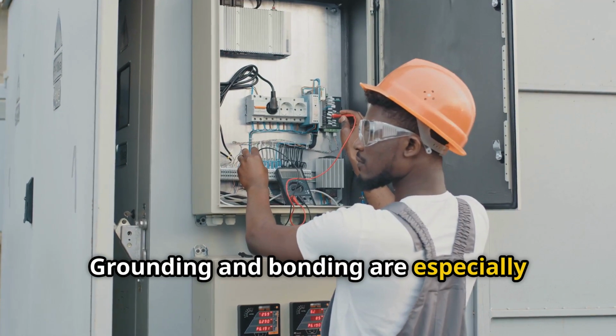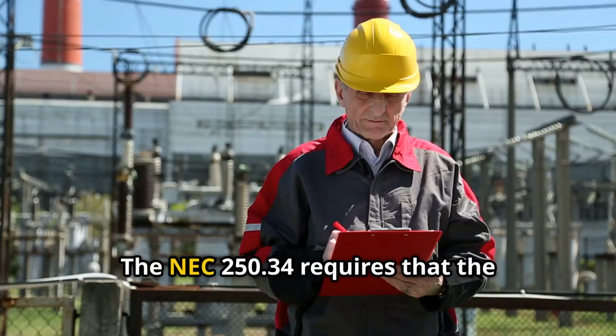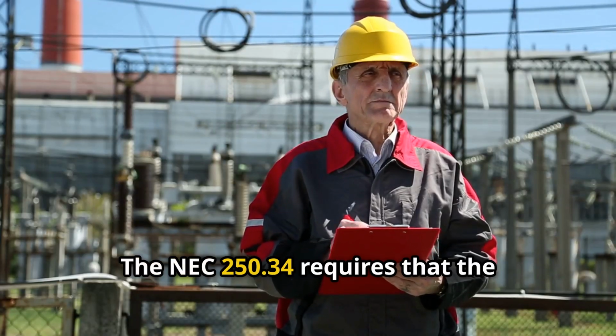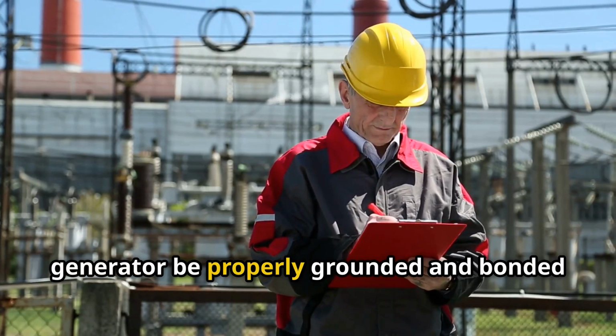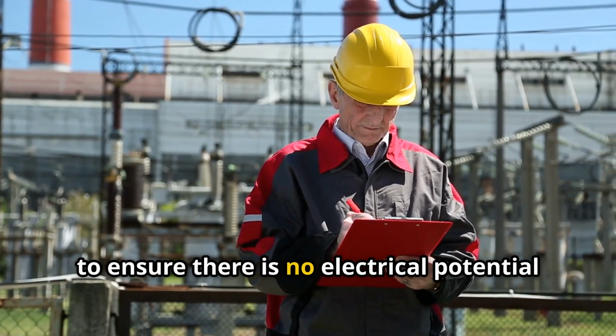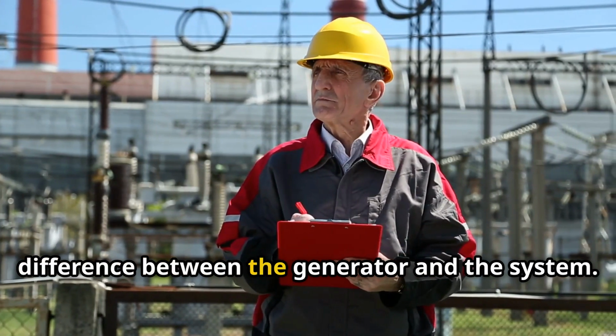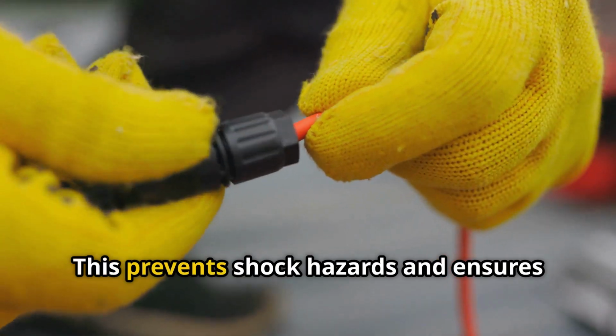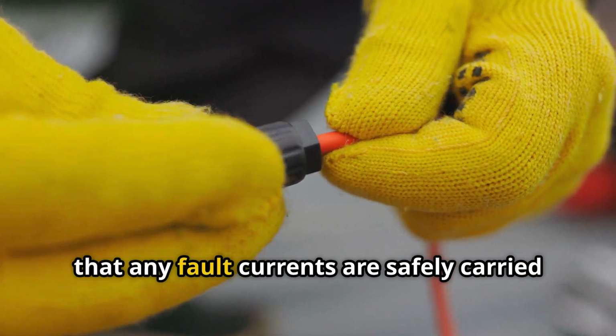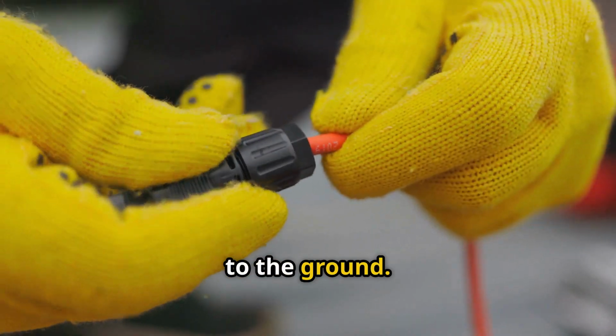Grounding and bonding are especially important for generators. The NEC 250.34 requires that the generator be properly grounded and bonded to ensure there is no electrical potential difference between the generator and the system. This prevents shock hazards and ensures that any fault currents are safely carried to the ground.